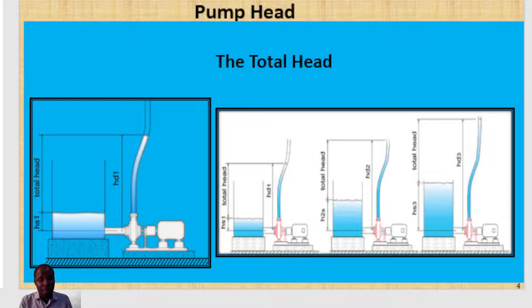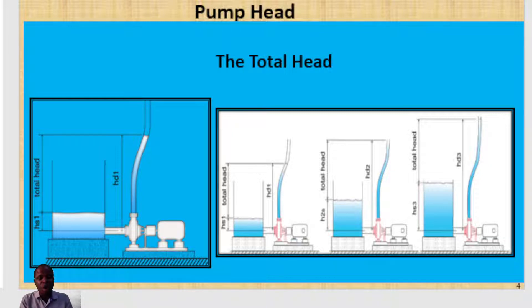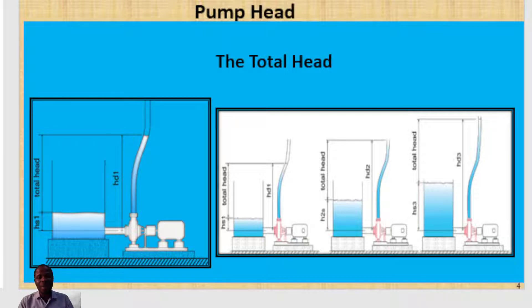That is why it is always advisable, when you are calculating the total head requirements, to calculate based on an empty suction tank — that is when you will need the pump to produce the most energy, because there is no potential energy available at that empty suction tank. With an empty suction tank, the liquid is not giving any help at all in the form of potential energy.